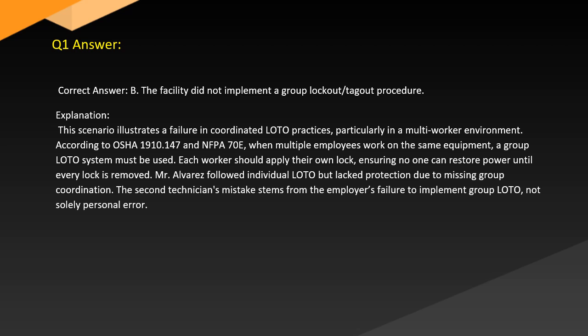Explanation. This scenario illustrates a failure in coordinated LOTO practices, particularly in a multi-worker environment. According to OSHA 1910.147 and NFPA 70E, when multiple employees work on the same equipment, a group LOTO system must be used. Each worker should apply their own lock, ensuring no one can restore power until every lock is removed. Mr. Alvarez followed individual LOTO but lacked protection due to missing group coordination. The second technician's mistake stems from the employer's failure to implement group LOTO, not solely personal error.